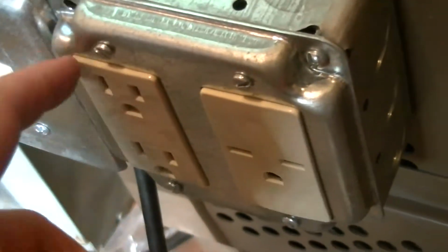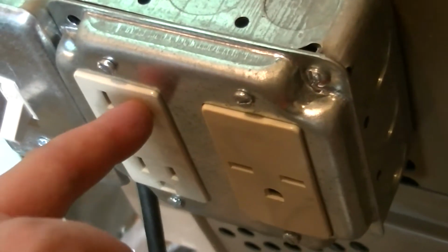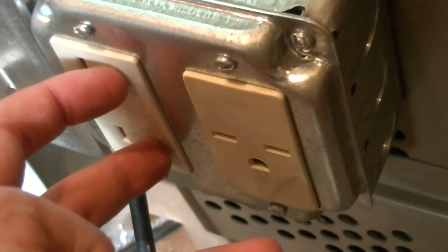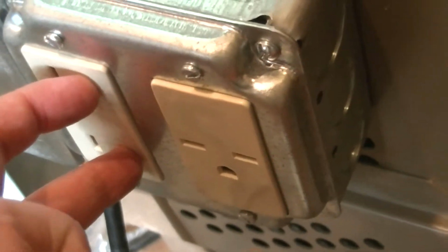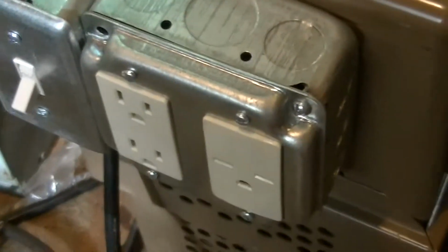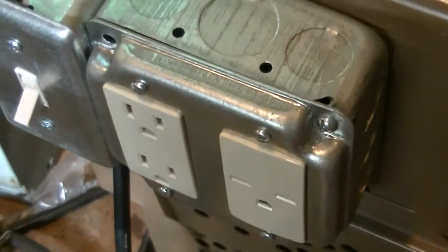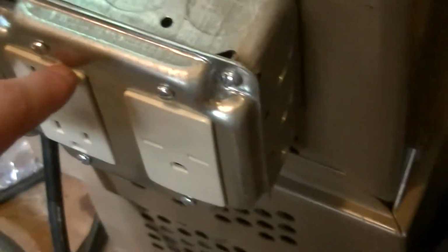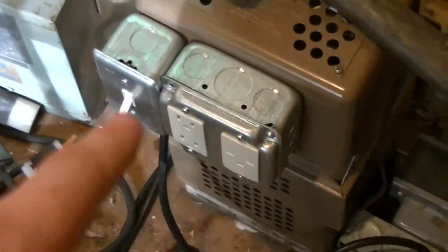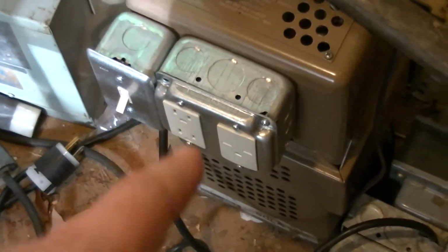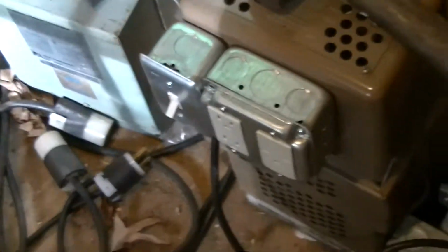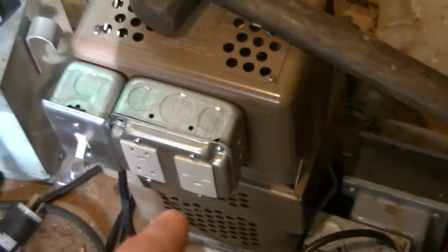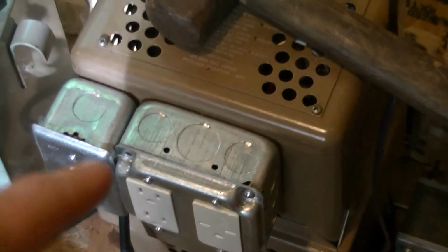And what I did for load balancing purposes is I split the hot in the receptacle, so there's 240 volts between the hot positions on that receptacle. If you're not familiar with that, there's an internal bonding jumper between both the hot connections and the neutral connection, so I broke the one for the hots for obvious reasons, otherwise it would short out the transformer. And also there's a main on-off switch.